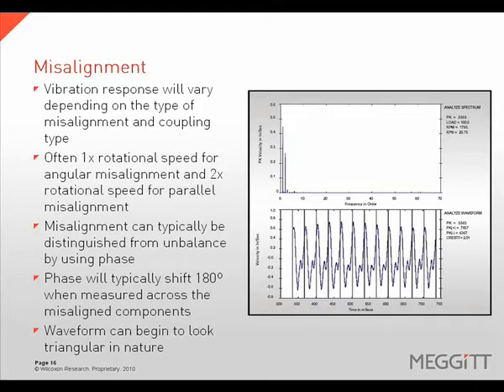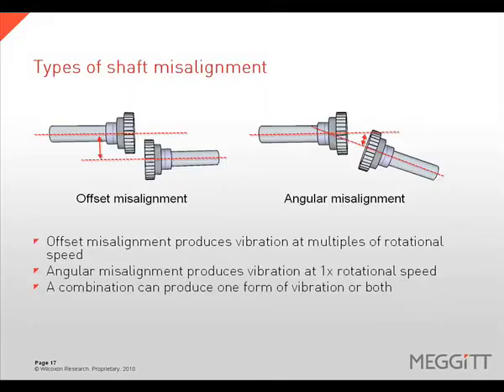Angular misalignment will often have a 1 times rotational speed response, while parallel misalignment will have a 2 times rotational speed response. Phase measurements will help distinguish misalignment from other faults like unbalance — the phase readings will shift 180 degrees when measured across the misaligned components. The waveform will also begin to look triangular in nature.